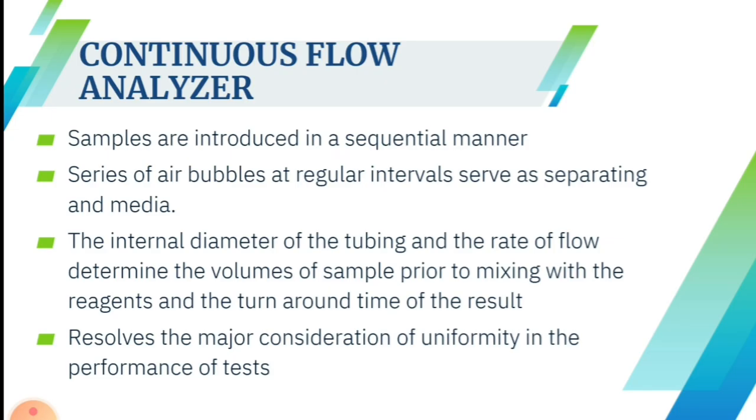So in continuous flow, liquids such as the reagents, diluents, and samples are pumped through a system of continuous tubing. Samples are introduced in a sequential manner, following each other through the same network. As I have mentioned earlier, a series of air bubbles at regular intervals will serve as a separating and cleaning media. Continuous flow therefore resolves the major consideration, uniformity and performance of tests, because each sample follows the same reaction path.